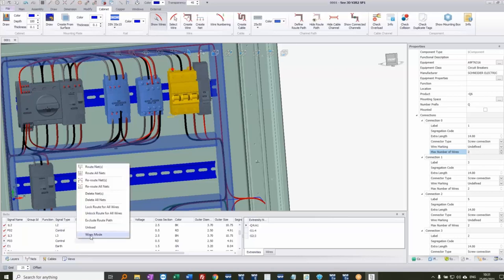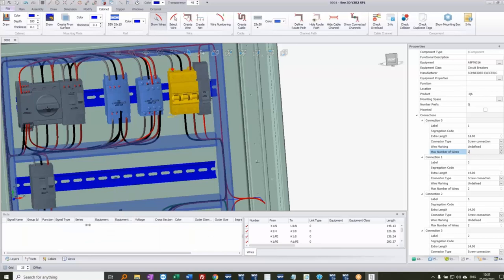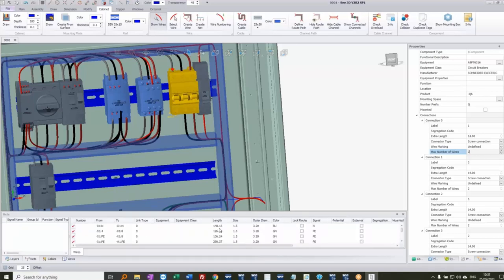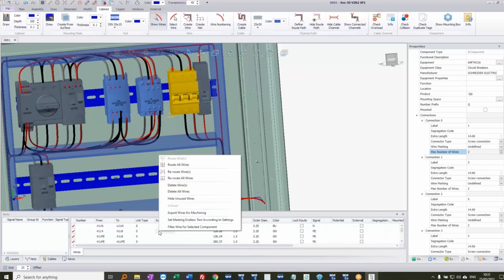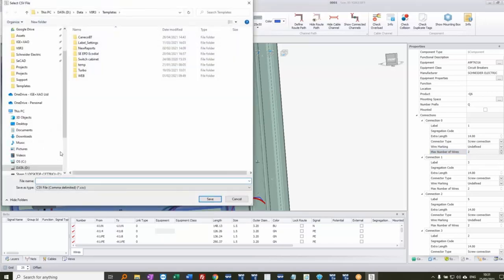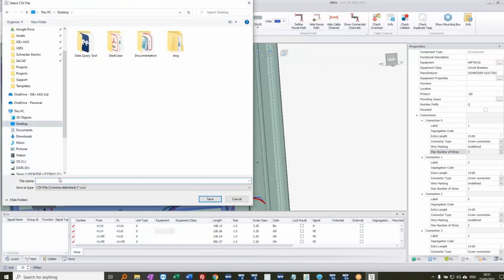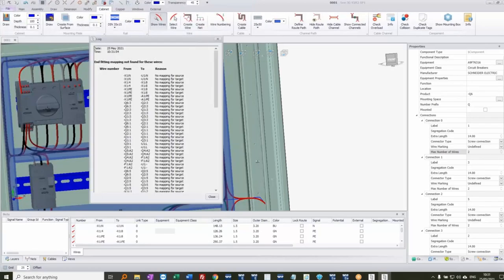I can right-click and go into wires mode, which lists all individual wires with their length, size, outer diameter, color, and signal name. To send this to a cutting machine, I right-click and choose 'Export wires for machining', saving it as a CSV file. There is a mapping option to add additional instructions per wire type, but I haven't set that up here, so it just warns me about the missing mapping.